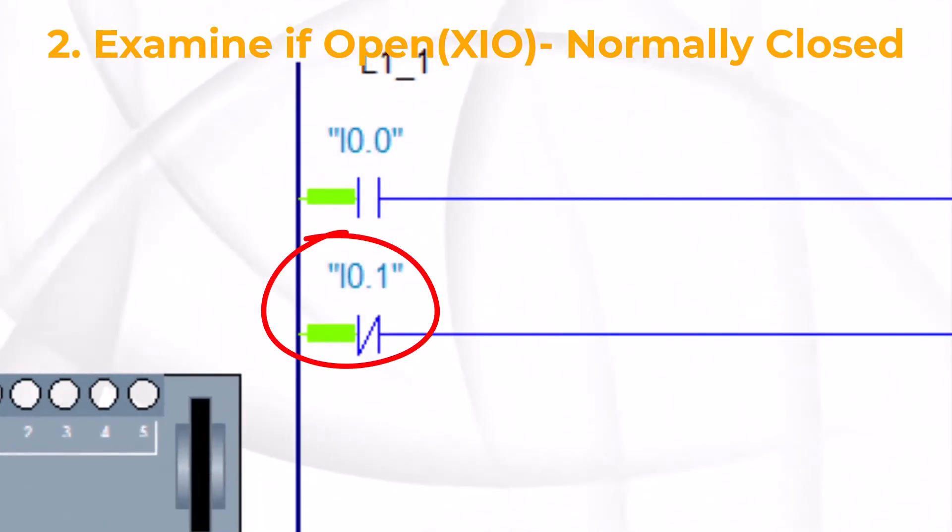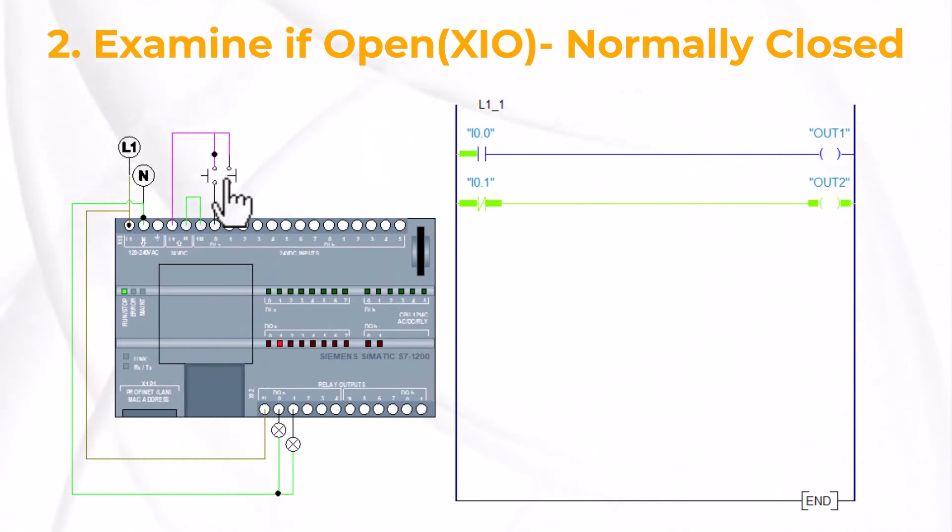XIO, examine if open or normally closed contact. The XIO instruction looks and operates like a normally closed relay contact. There is a memory bit associated with each XIO instruction that is linked to the status of an input device or internal condition.